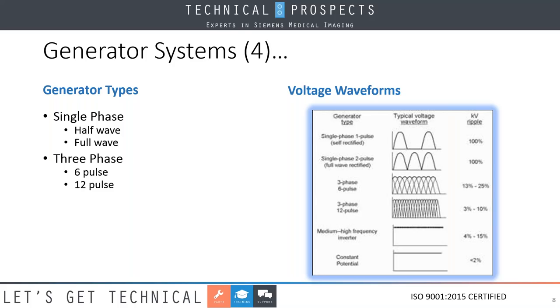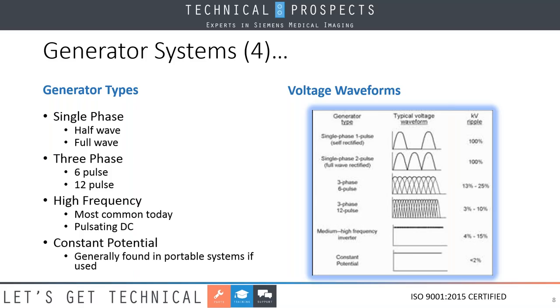In three phase, we have 6 and 12 pulse, and the purpose of all this here is to lower the ripple, because the better we control the ripple, the better quality of KV that we get. Our most common today is high frequency, and that's been around since the late 70s, early 80s. It is around in almost all systems today, and this basically uses a pulsating DC. As you can see, just from the ripple itself, it almost looks like a straight line because of the higher frequency. We're no longer being tied to the 50 or 60 hertz of our AC incoming power. The last one is typically found in portable systems, and that is a constant potential type system.